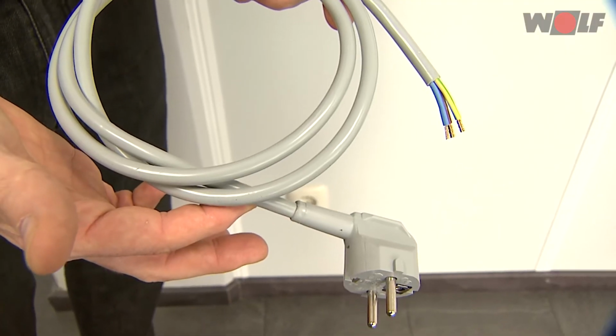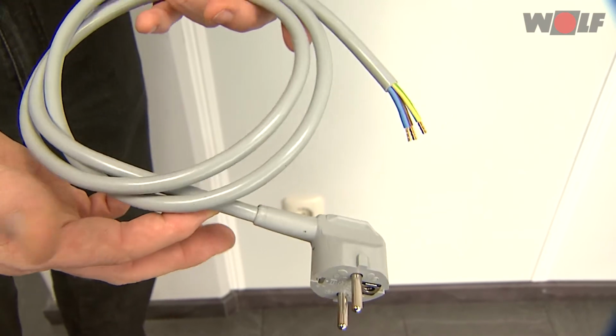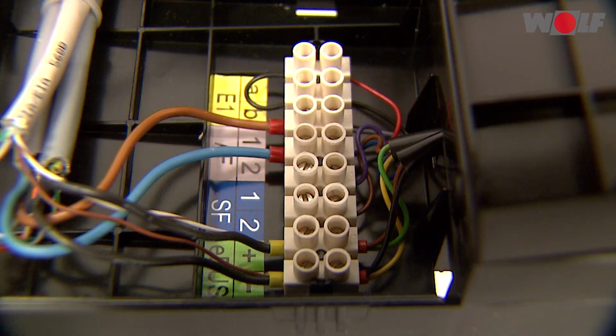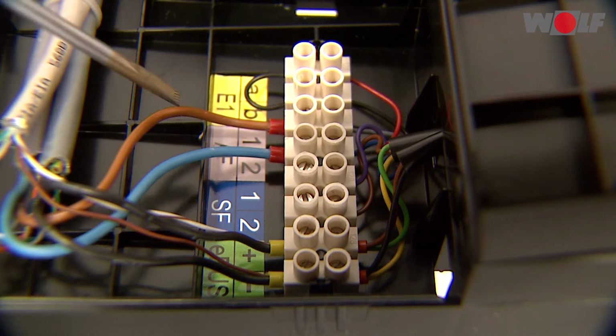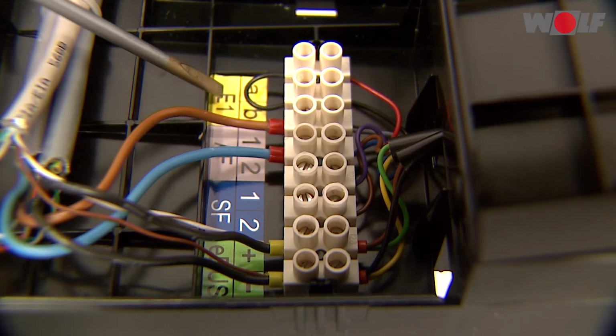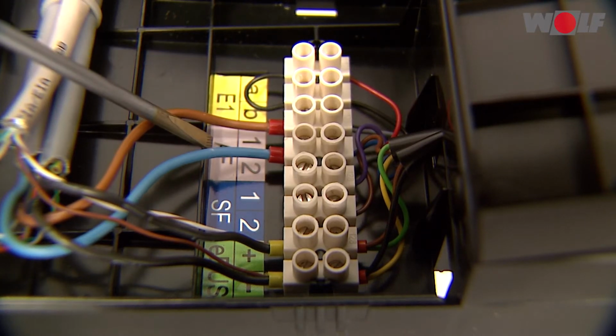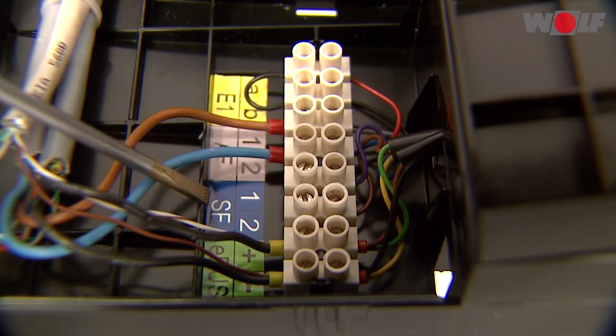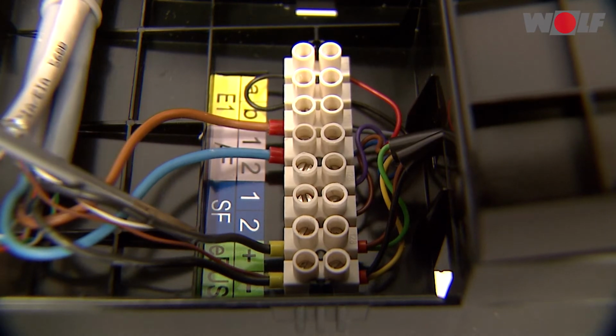Power supply cable 230 volts, 50 Hz. Room thermostat input. Please note, no external voltage must be connected to input E1 as this would destroy the PCB. Outside temperature sensor. Cylinder temperature sensor. E-bus.